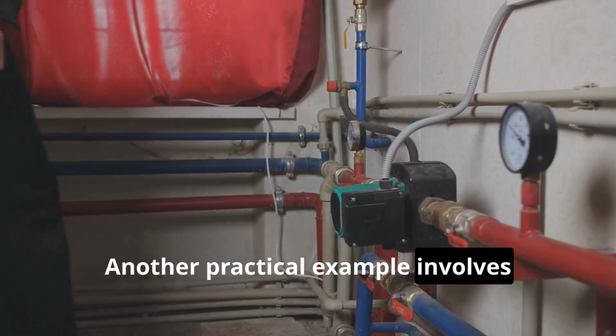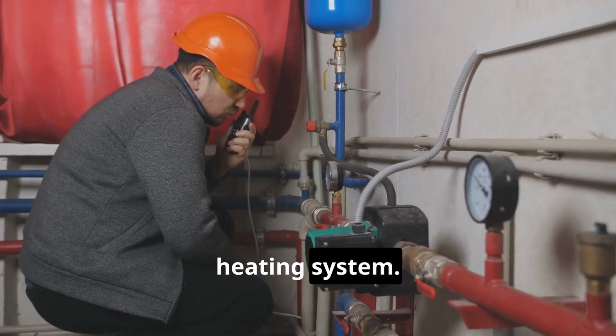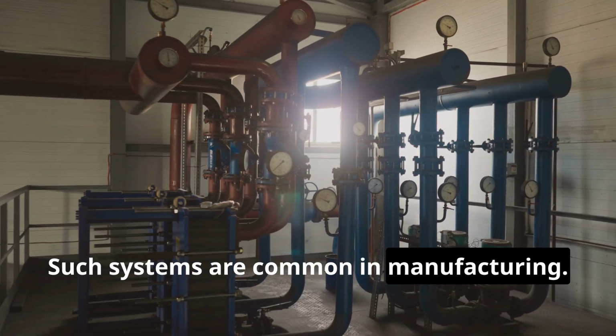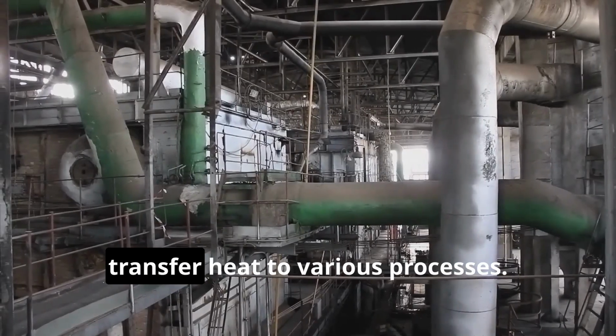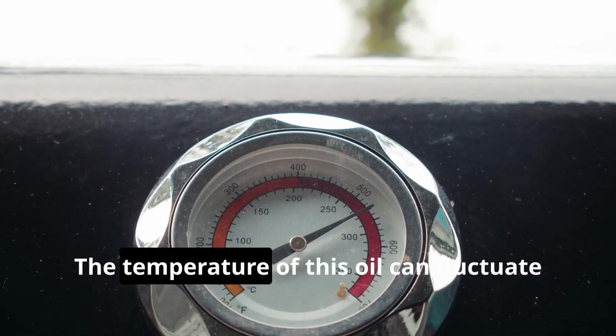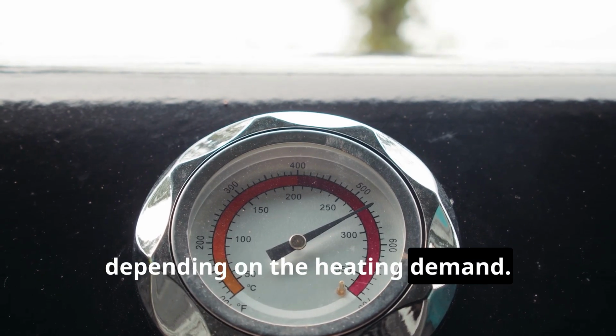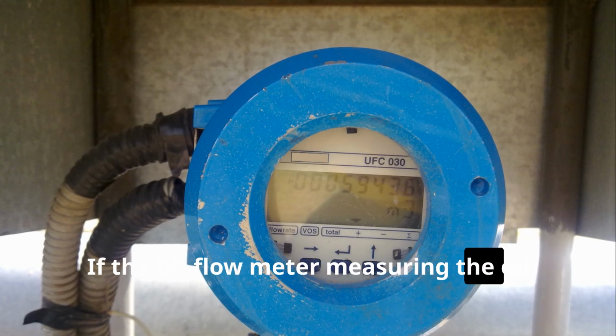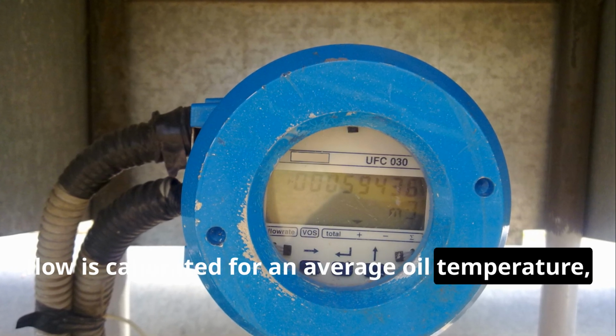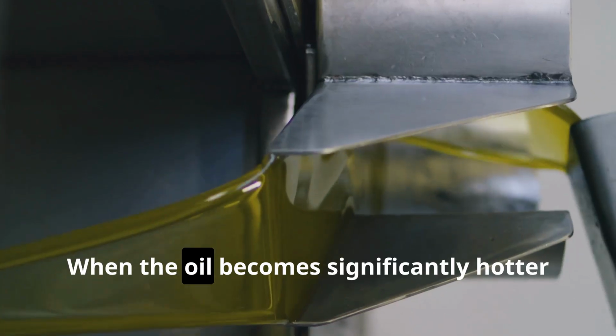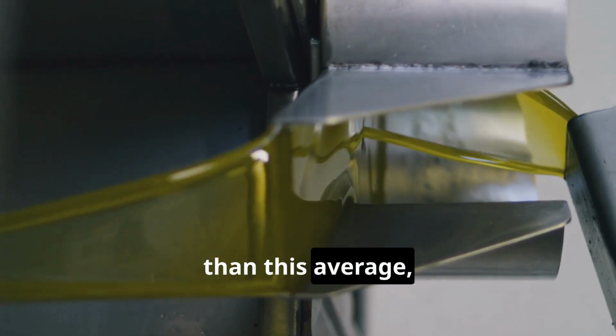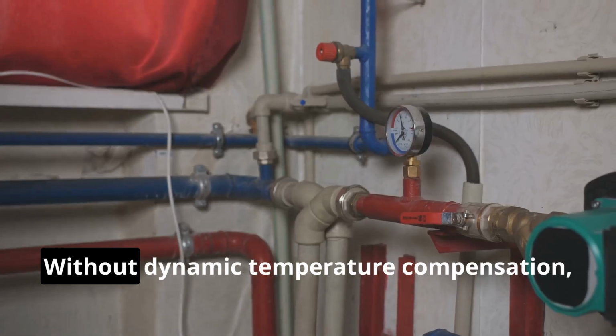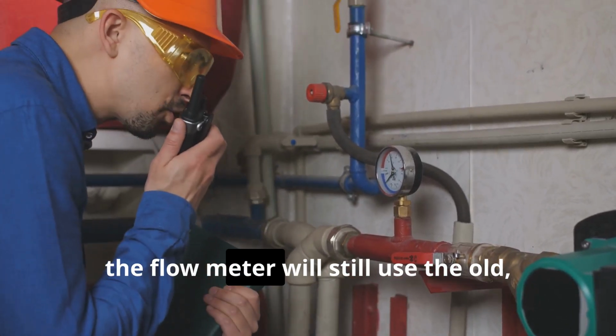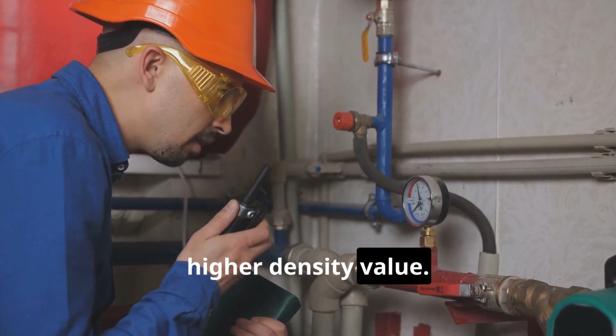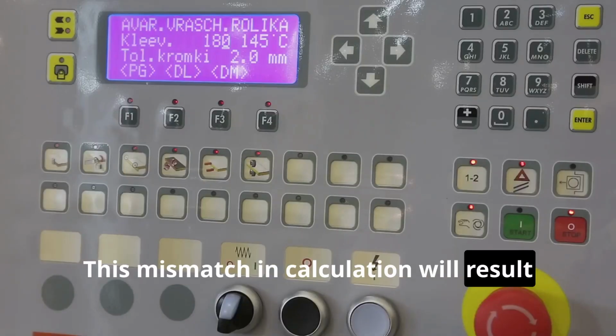Another practical example involves temperature variations in a hot oil heating system. Such systems are common in manufacturing. The oil is heated and circulated to transfer heat to various processes. The temperature of this oil can fluctuate depending on the heating demand. If the DP flow meter measuring the oil flow is calibrated for an average oil temperature, problems arise. When the oil becomes significantly hotter than this average, its density decreases. Without dynamic temperature compensation, the flow meter will still use the old higher density value. This mismatch in calculation will result in the meter reporting a flow rate that is erroneously high.